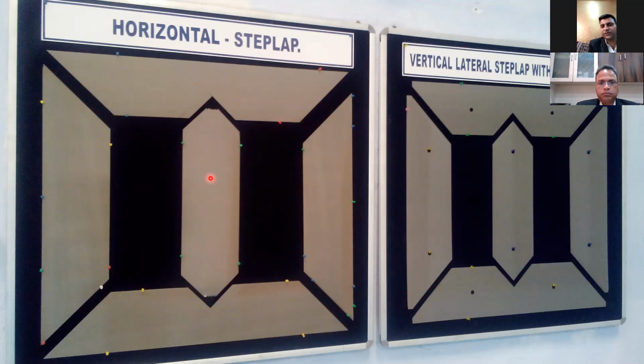It is not possible, because lamination may fall down, since in vertical design these step laps will be in plus-minus side in vertical position, and there might be a chance that the last piece may fall down between the limb. So this is the simple reason why a hole is mandatory in vertical design.